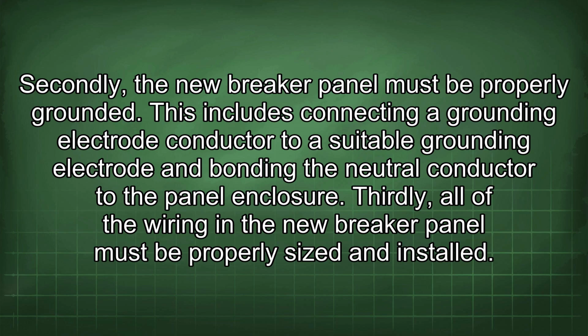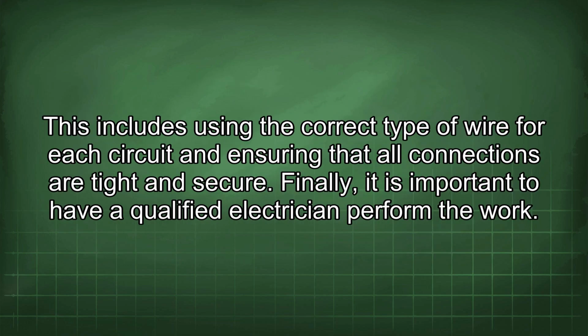Secondly, the new breaker panel must be properly grounded. This includes connecting a grounding electrode conductor to a suitable grounding electrode and bonding the neutral conductor to the panel enclosure. Thirdly, all of the wiring in the new breaker panel must be properly sized and installed. This includes using the correct type of wire for each circuit and ensuring that all connections are tight and secure. Finally, it is important to have a qualified electrician perform the work.